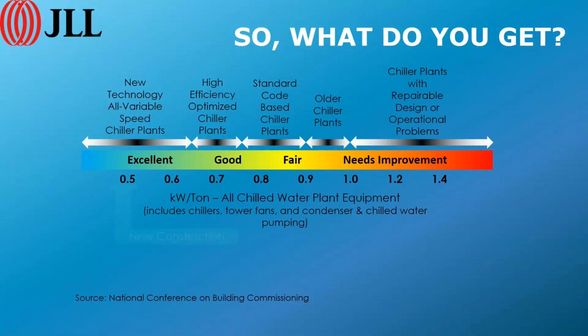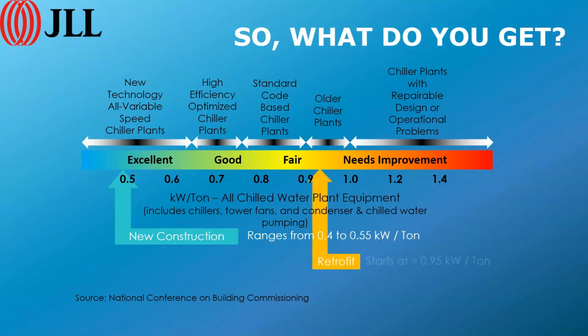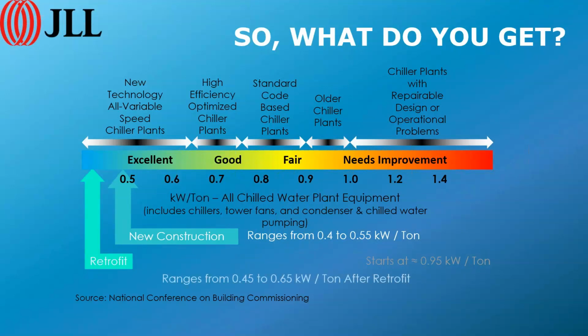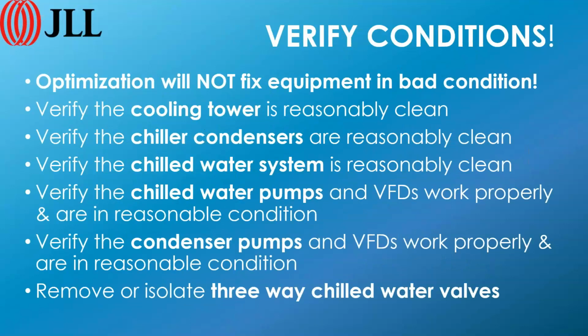Again, we're going to start with new construction plants, which generally run around 0.4 to 0.5 kW per ton. Retrofits, when we see them, start out somewhere around 0.95. Some of them we'll see up around 2 kilowatts per ton, but it's pretty typical to see an existing plant running around 1 kilowatt per ton. And we want to get that down to somewhere in the range of 0.45 to 0.65 kW per ton. That's the goal. First step in the process is to verify conditions.